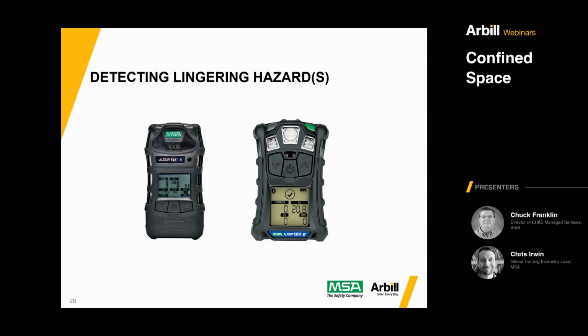The detector on the right, the 4XR, also has its strong suits. As mentioned, it's a little smaller, and to start with it's diffusion based, meaning there's no pump built into it. You would not hear that whirring noise. But the air that comes into contact with those three white areas near the top, which are actually water filters, gets tested in the exact same way using the exact same sensors that are in the 5X. But this is a wearable device, so on the back side there's a clip, and you would typically clip it onto your full body harness. We'll take a look at a harness for confined space entry a little further down the line here.